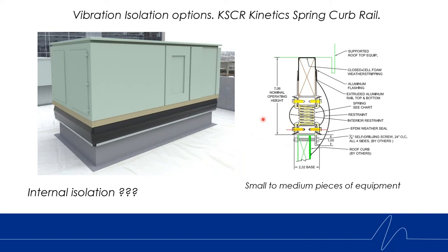After the isolation pad, we do have a lightweight Kinetics spring and curb rail. This comes as a curb and a rail — the unit sits down on top, and it comes with a weather seal that covers up all the springs. The unit sits on top of the top rail, compresses the springs, and the springs absorb vibration from the casing and equipment inside the air handling unit. Now, we know that spring and pad worked really well together, but unfortunately spring and spring do not work well together. So you must lock out your internal springs when setting that air handling unit on a spring rail.